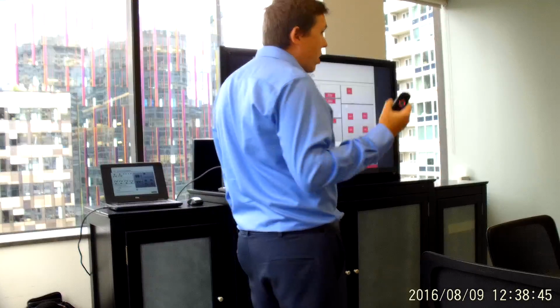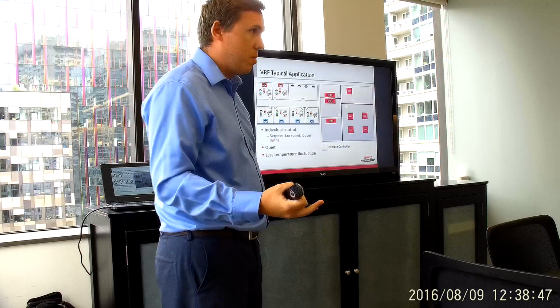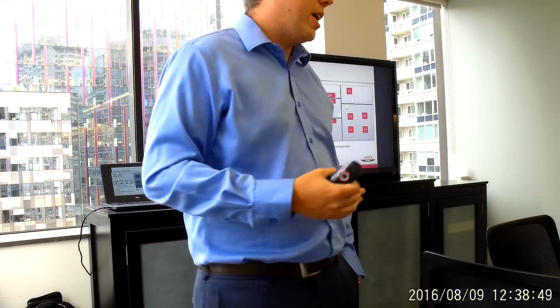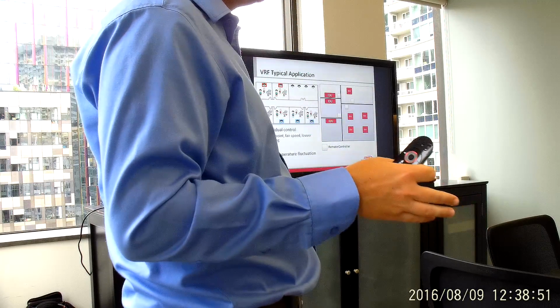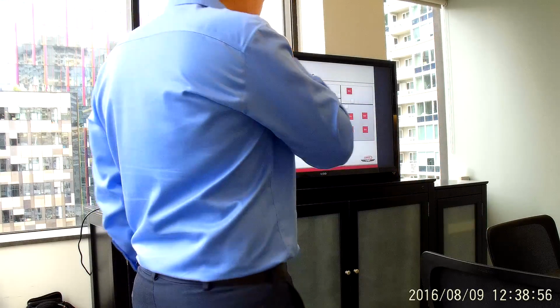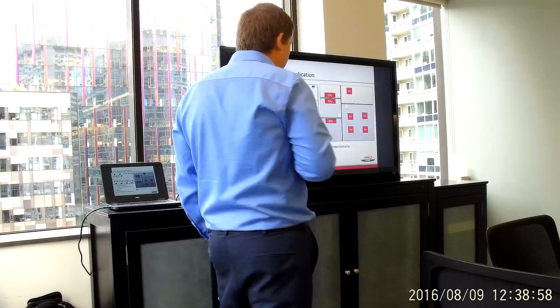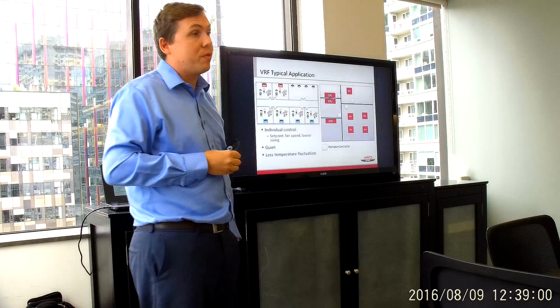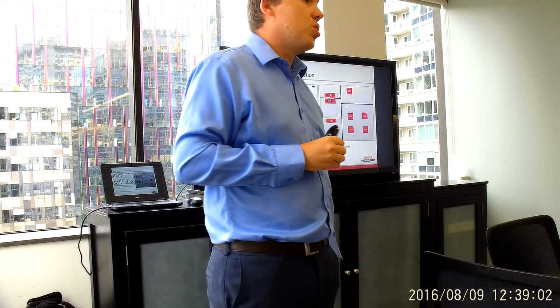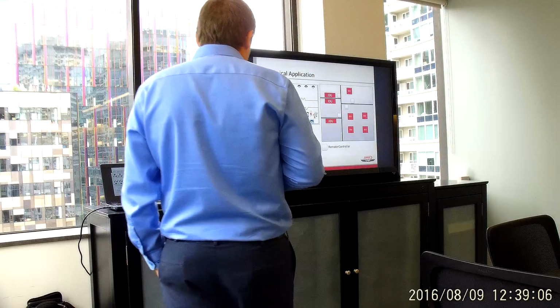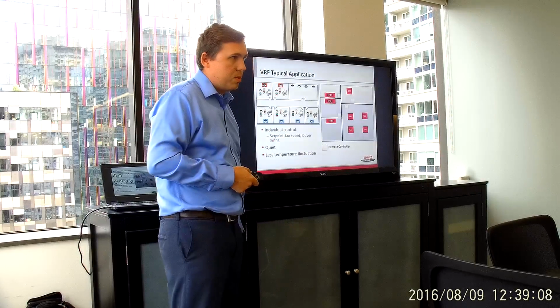Because very simply, for a school application, for example, you've got a high amount of fresh air that's got to come in there. You've got to deal with all that. And a rooftop unit, ton per ton, is by far the least expensive system you're going to put in. It may not be as close controlled as the VRF system. It may not be as energy efficient, but it is still a good solution and it will do the job properly. It's another thing to consider when you're looking at fresh air for these systems.